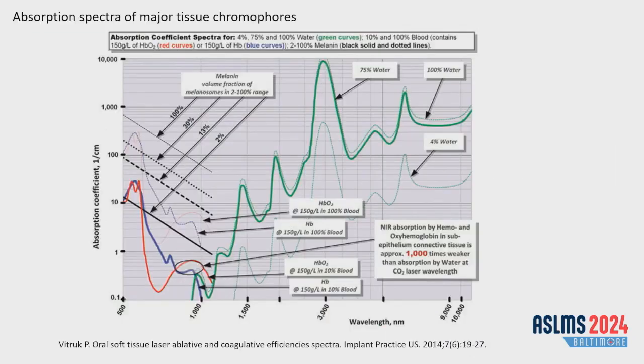What actually absorbs directed energy in tissue to make it interact? Here are shown absorption spectra of the most important chromophores in biological tissues. By far the most important of them is water, which of course is the basis of all biological tissues. As you can see, it has absorption peaks around 3 microns and around 10 microns, which explains why lasers such as erbium YAG and CO2 are so popular.